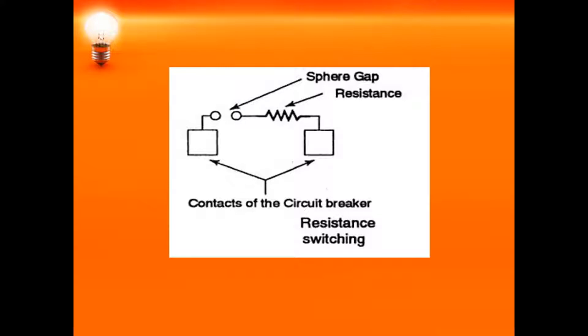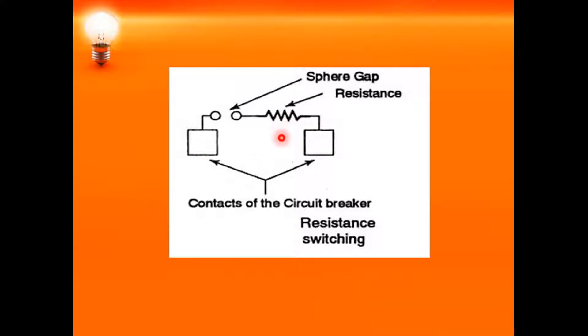To reduce this restriking voltage, we connect a resistance across the circuit breaker contacts — specifically, a resistance along with a sphere gap across the contacts. The way in which this resistance is connected, so that the arc current follows the path of this resistance, is called resistance switching.